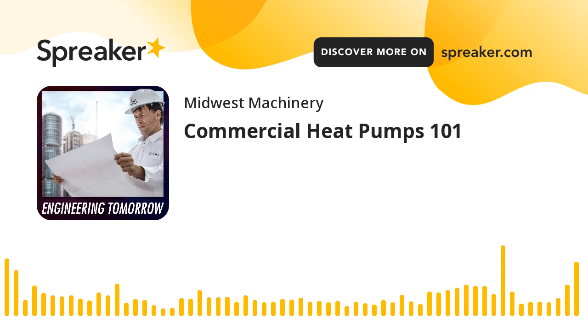So if you have 300 units on a project, you go in and add up the heat of rejection on all those units for the cooling side. So not just the load in the room, but you've got to take the heat of compression into account too. So you look at the heat of rejection of all those units, add them all up, and let's just say it gives you 300 tons of cooling necessary for those units. Once you have that number, you can do a couple things. You could say, okay, I'm going to size my plant to handle all 300 tons. I'm going to size my cooling tower for 300 tons. And that's safe. That gets you what you need to handle all those units.